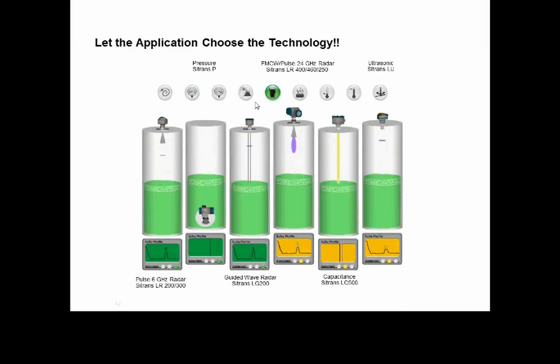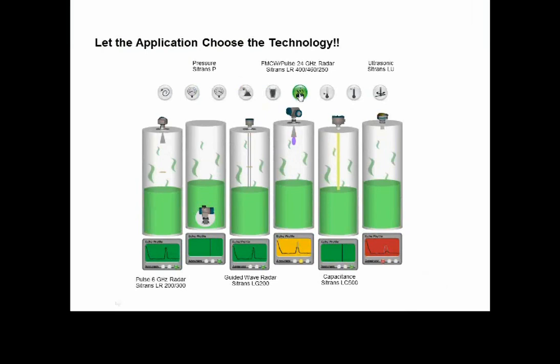What's the quality of the foam? Is it dry foam? Is it thick? There's a difference between measuring something like a light sudsy soap and something like a beer foam. Okay. The vapors. If we have vapors, it doesn't bother radar, but it causes major problems for ultrasonic, in that when there's vapors in the atmosphere, the speed of sound changes, and that throws off an error. That actually throws the unit off. If that's consistent and steady, we can make adjustments for it, but it's still a challenge.